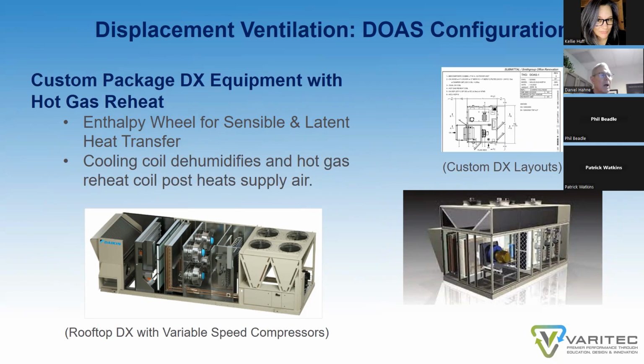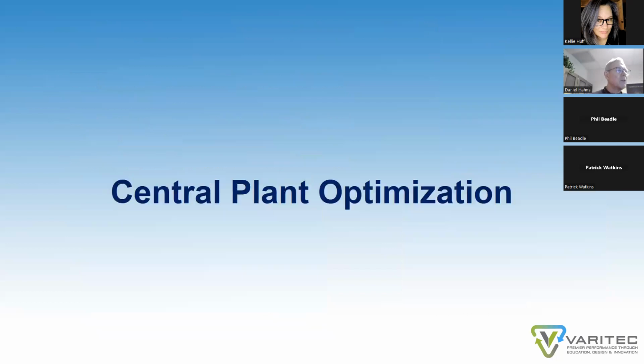And by using hot gas reheat technology in a DX 100% outside air unit, you can control the leaving air temperature after dehumidifying air at the chill water coil by using the heat of rejection off of a compressor and allow that heat to pass through a bypass hot gas reheat coil that will post-heat the air off the chill water coil without using any other form of supplemental heat. You've already paid for the energy in the cooling cycle, so you can use that to post-heat the supply air to your assigned 62 to 65 degrees.